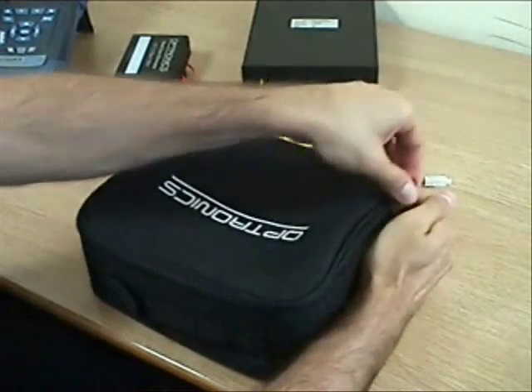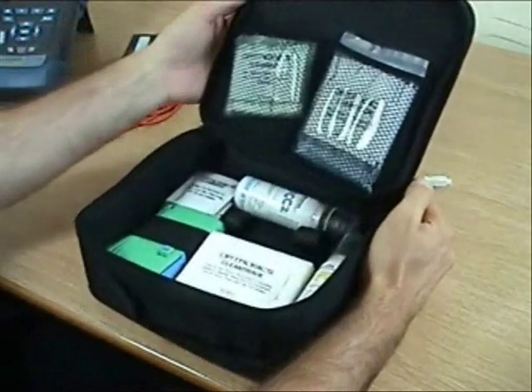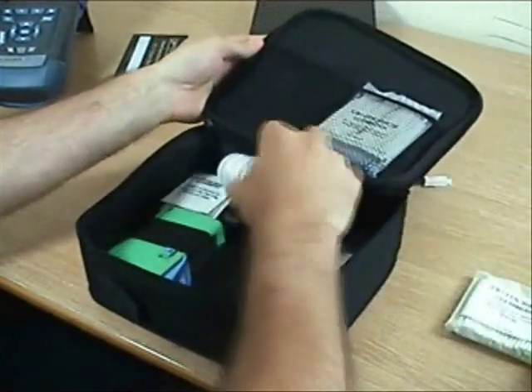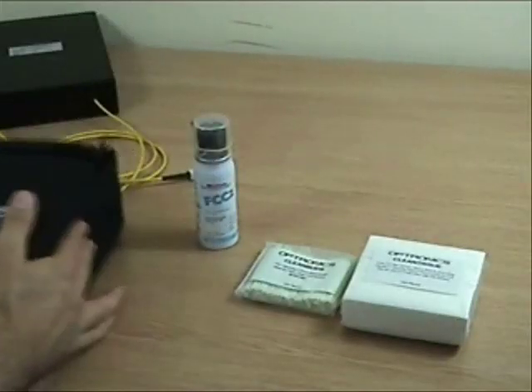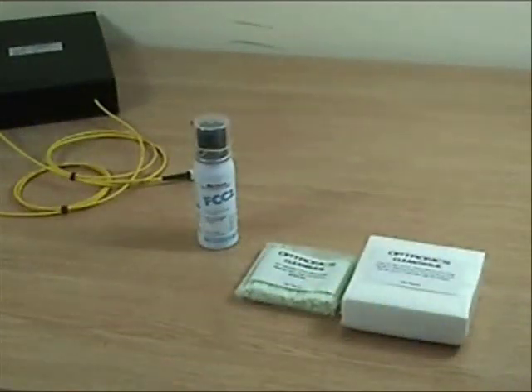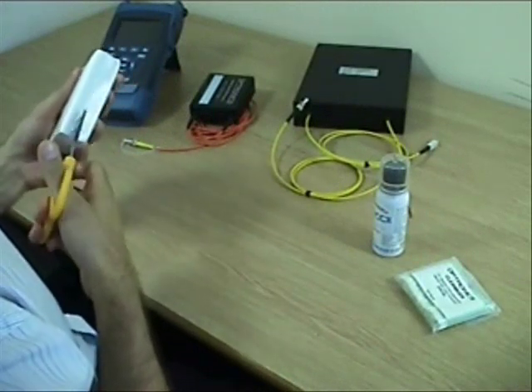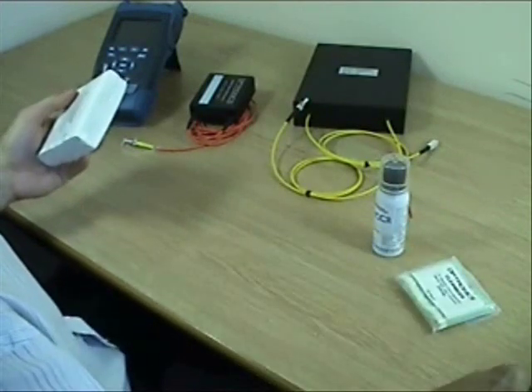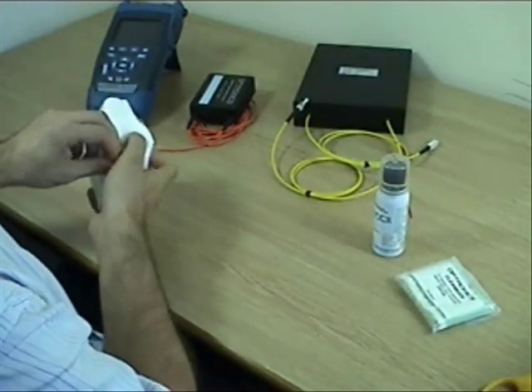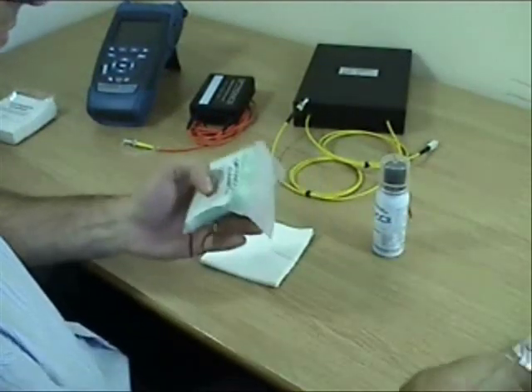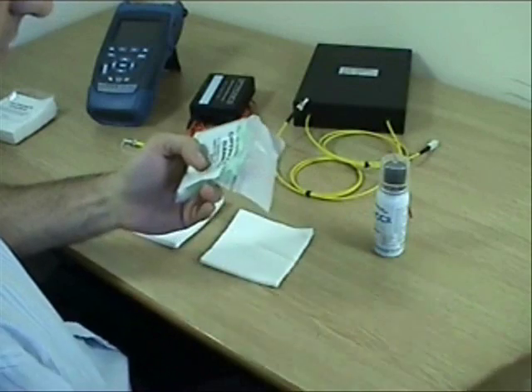Opening the Optronics cleaning kit reveals all the items required to ensure the fibre optic installation is kept as clean as possible. We will use the 2.5mm buds, lint free wipes and connector cleaning fluid. Remove the plastic covering from the lint free wipes and take a few sheets to create a pile which we will use with the cleaning fluid and a pile which we will leave dry. Remove two of the 2.5mm buds.